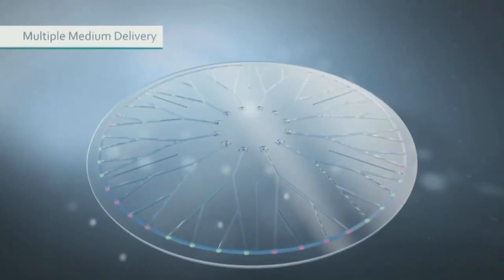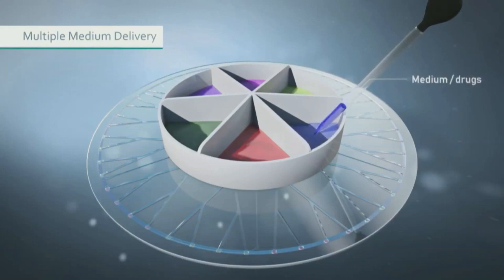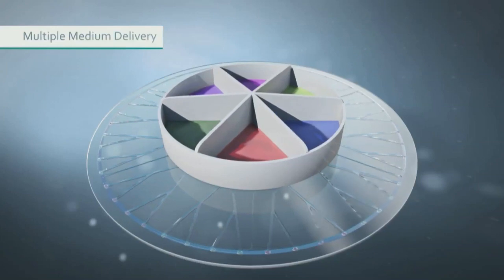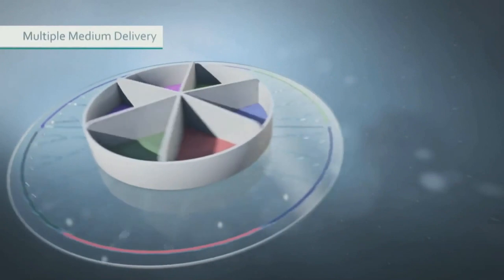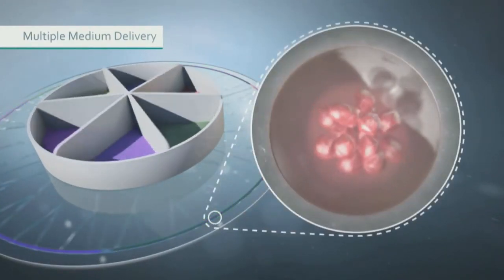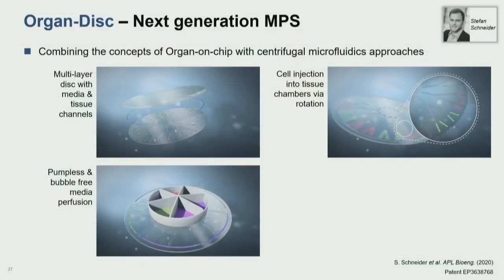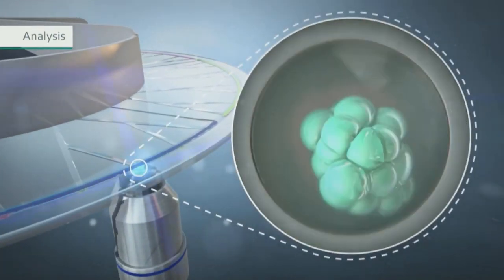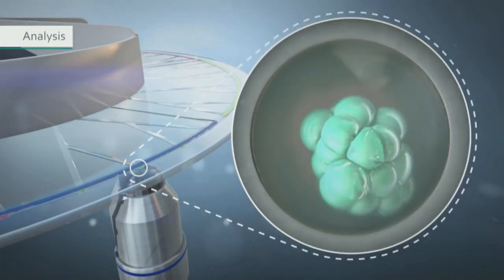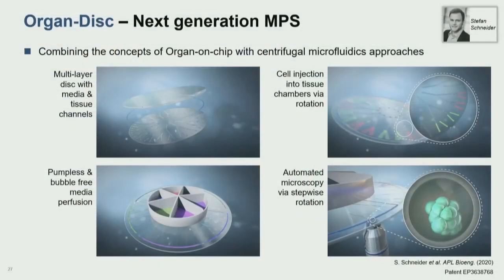The same concept works for media perfusion: we add a reservoir to the center with fresh media and raised reservoirs on the outside, then start a slow rotation of the disc. This drives media from the inside through the media channels to the outside, perfusing all tissues simultaneously without any external pump. The symmetry of the system also allows us to use just one readout — one microscope or optical fiber — and sequentially rotate the disc to image all individual tissues one after another.